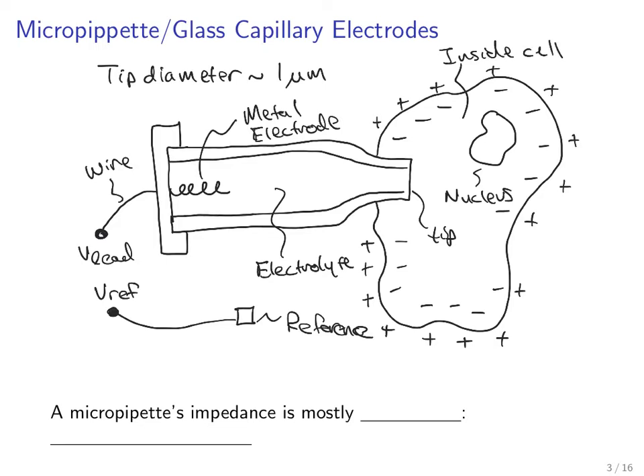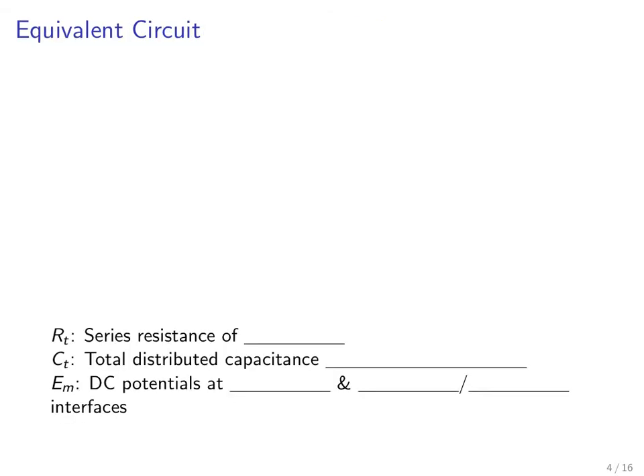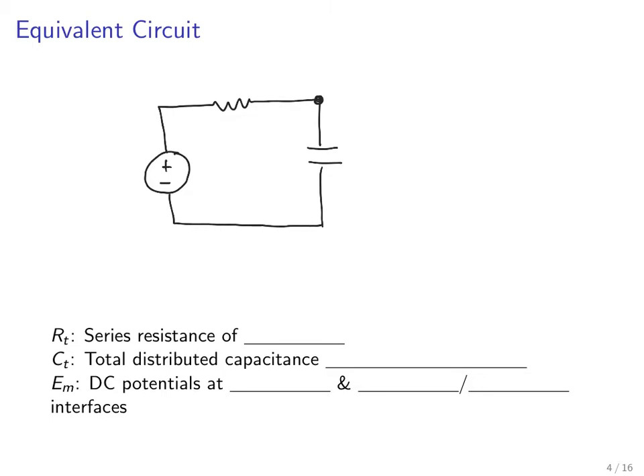The micropipette's impedance turns out to be mostly resistive, with a resistance that's somewhere between 1 megaohm and 100 megaohms. And here's an equivalent circuit for a micropipette electrode inserted into a cell. You have this voltage source, which is time varying. You have a resistance, a capacitance. You also have a half cell potential. So we'll call this capacitance C sub t, the resistance R sub t, and the half cell potential E sub m.